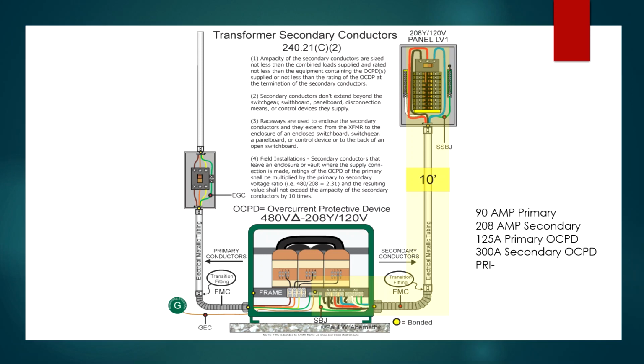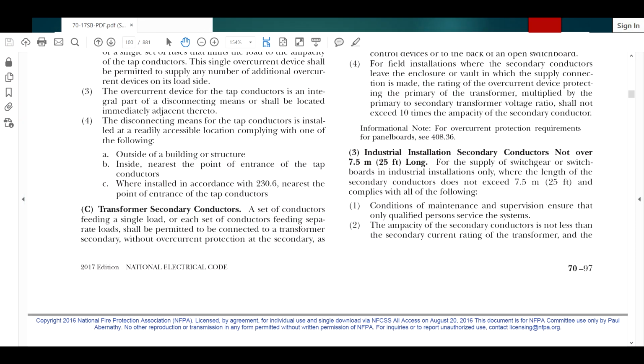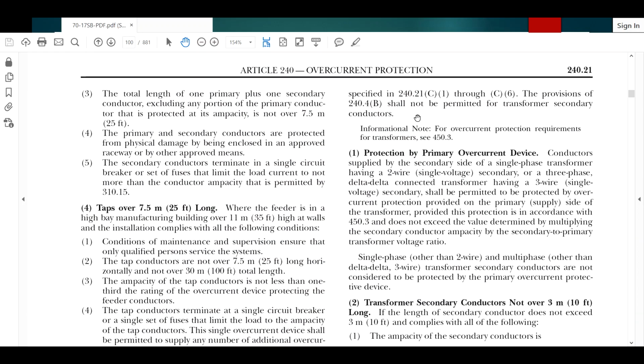All right, so let's go back and look at the rules for C1. Let's finish reading what we're working on. Okay, so it says that I could have the secondaries feed multiple loads. Shall be permitted to be connected to a transformer secondary without that overcurrent protection, as we just talked about. It says, as specified in 240.21 C1 through C6. So you have 6 different options here for these secondary conductors. It reminds us, again, that the provisions of 240.4b shall not be permitted for transformer secondary conductors.